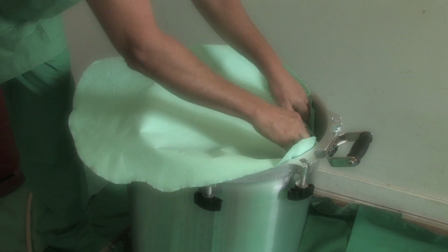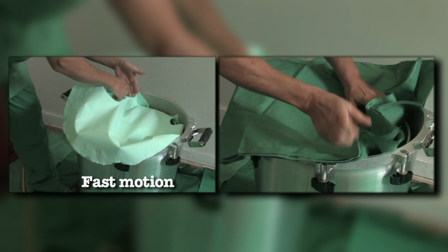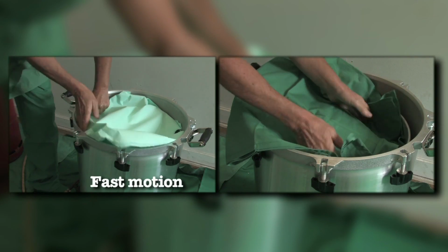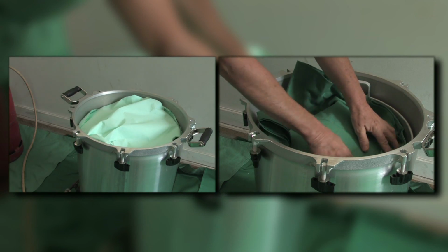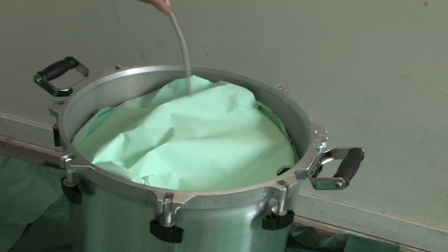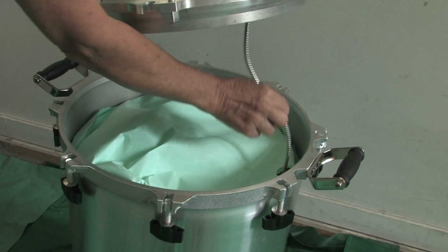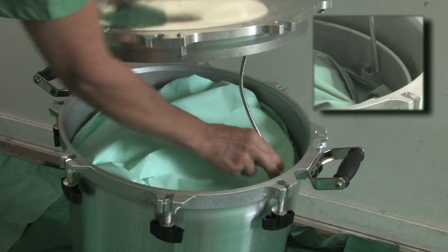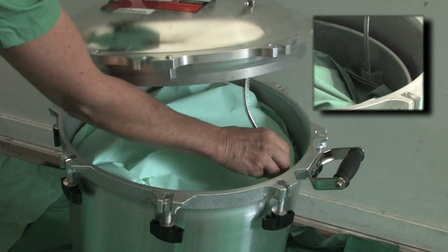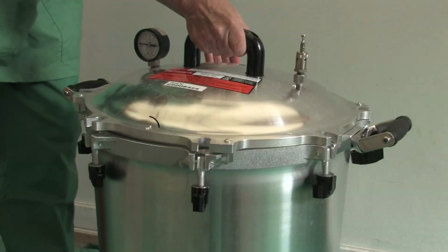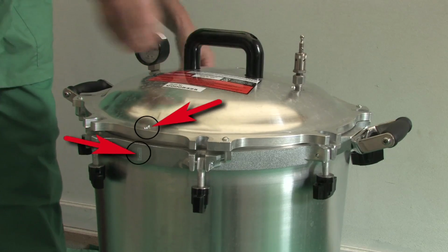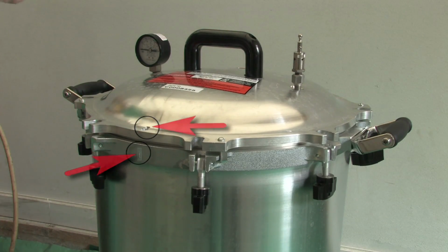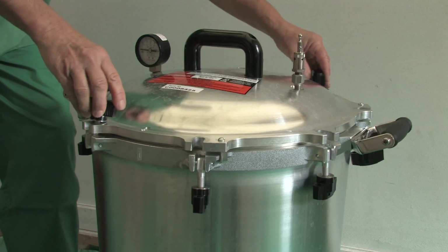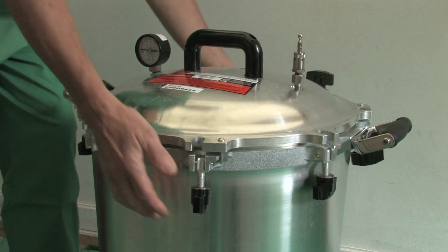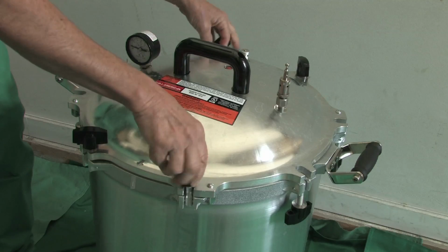3. Cover the load with a piece of crepe sterilization paper or an absorbent cloth, leaving a space for the flexible metal tube. 4. Position the cover, making sure that the metal tube attached to the cover is inserted in the basket's guide channel. The marks on the cover and the outside of the chamber should line up. 5. Tighten the wing nuts manually, 2 by 2, in diametrically opposite pairs.